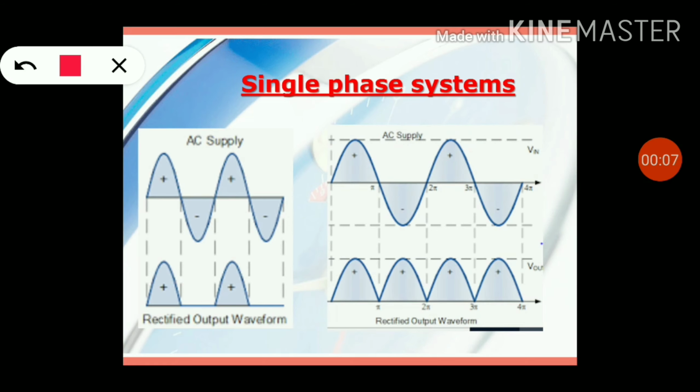AC power supplies X-ray units with a sinusoidal current that results in peaks and troughs. That leads the X-ray tube to produce X radiation only in half of this cycle. So in a single phase system, the high voltage generator converts AC power with a half or full wave rectified supply.